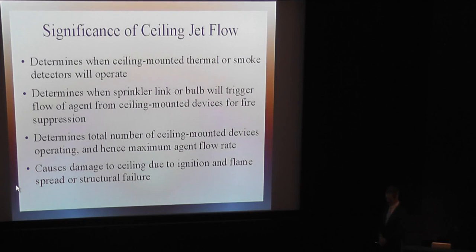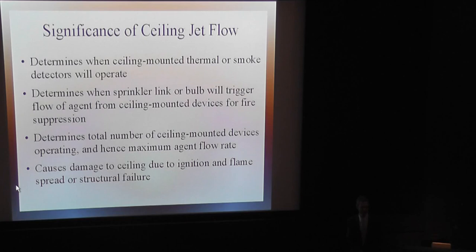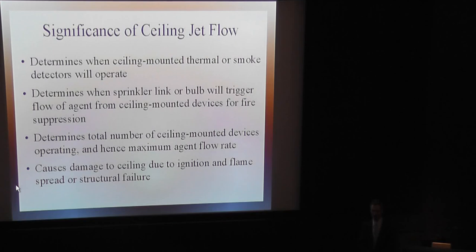The ceiling jet flow itself is a relatively thin flow near the ceiling, fast moving compared to the rest of the hot gas layer. That flow is going to determine when the ceiling-mounted device is going to activate, whether it's a sprinkler, fire detector, smoke detector, or whatever. The ceiling jet's velocity, temperature, and thickness will determine how many of those devices ultimately are activated.